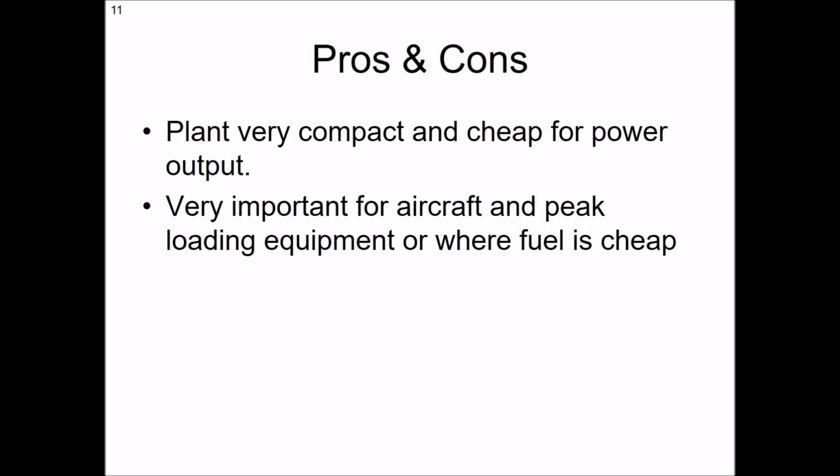Relatively speaking, the plant is exceptionally compact, and I'm going to be careful with the word cheap or cost effective, but they can be a lot more cost effective than things like steam plants, though that's all relative. One of the key things is they are extremely compact, and when you see pictures of gas-fired power generation systems, you realise how small these things are compared to their steam equivalents. So this is very important for aircraft and things like peak loading equipment, where, again, the word cheap is a bit of a misnomer, but we want to quite quickly get power into the grid and get up to speed quite quickly. Gas turbines are a bit more flexible in that respect.